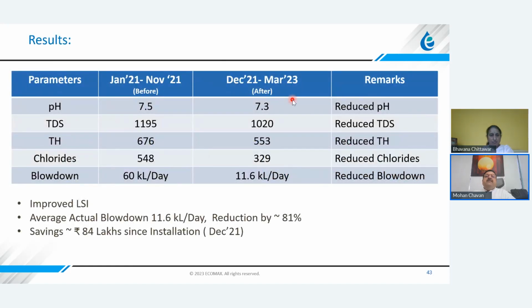And after implementing this technology, you can see the parameters before and after. Like I told you, 1195, so around 1200 TDS was down to about 1000. Total hardness from almost 675 to 550. Chlorides 548 to 329. And blowdown has reduced from 60 meter cube per day to 11.6 meter cube per day.